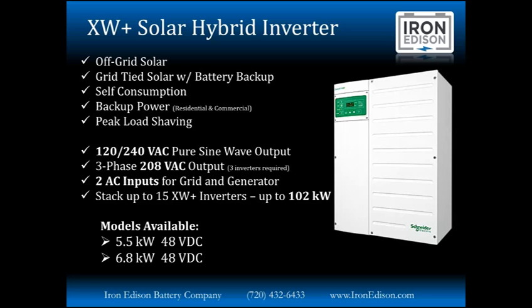And this inverter is configurable for 120/240 or the 3-phase 208 application. It does require 3 of the XW Plus inverters for the 3-phase because each inverter takes over 1 of the 3 phases. We can then stack multiple inverters together to create a system up to 102 kilowatts. A system of this size does require a specialty built external combiner box for all of the inverters and the solar array to come together. We're happy to help provide that design and provide that as part of a complete system.